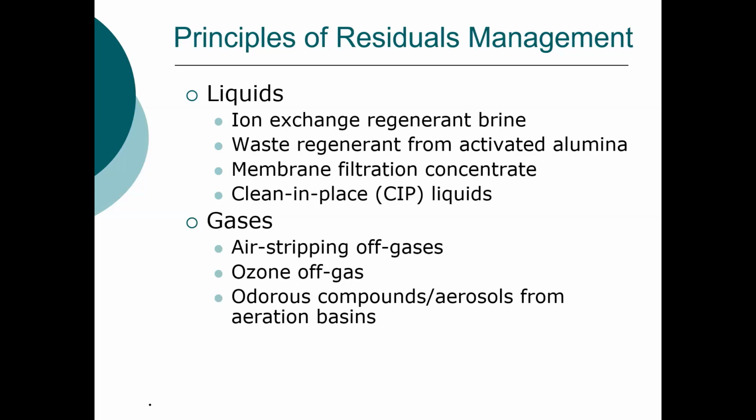Other liquids that we can have: ion exchange regenerant brine. This is a highly concentrated brine solution, and because you're regenerating on a cycling basis, it's essentially a batch process discharge, which also means that potentially, if this is going to the sewer, depending on the size of your plant, that can potentially overwhelm the sewage treatment plant.